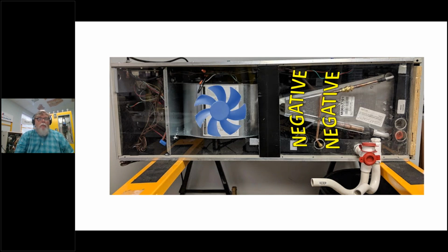If there is no trap, if the vent pipe between the trap and the unit is open, or a drain pipe, clean out pipe is open, it will actually suck air inward. If it sucks air in, it may not be able to drain.